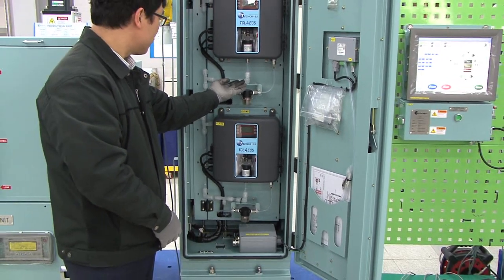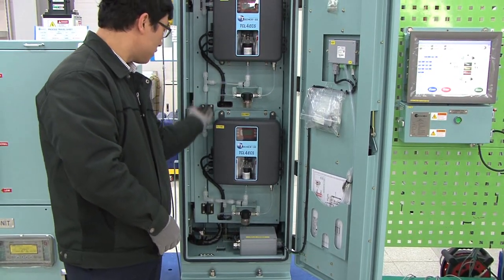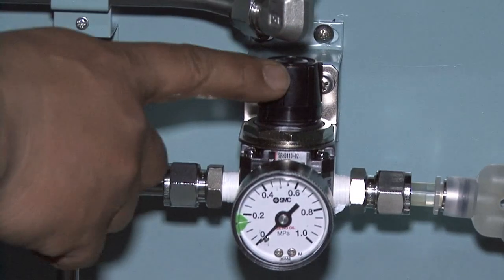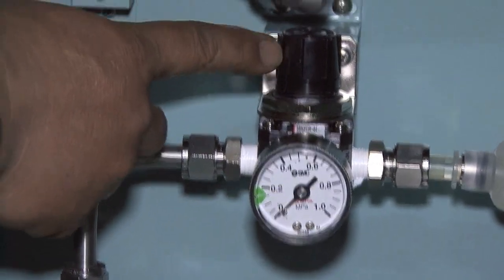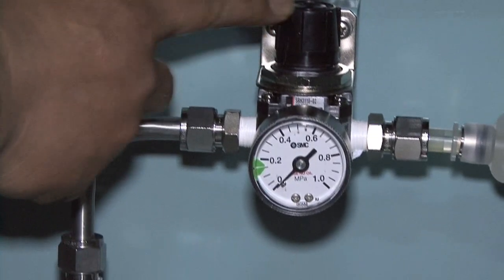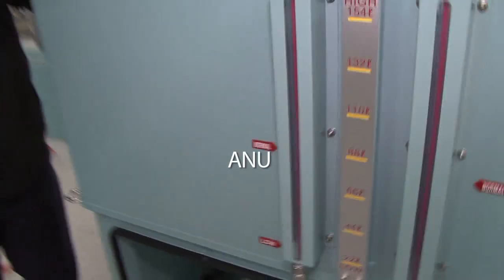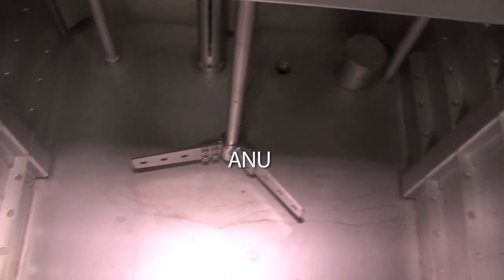1-2. Adjusting pressure level of regulator. Step 1. Set pressure level of regulator on the right side of circulating pump to 1.5 bar by adjusting dial of regulator. 2. ANU 2-1. Cleaning strainer of ANU tank.